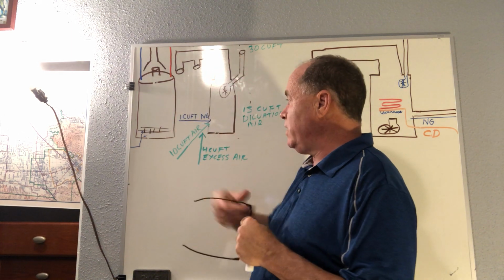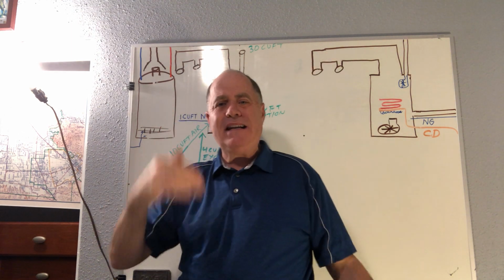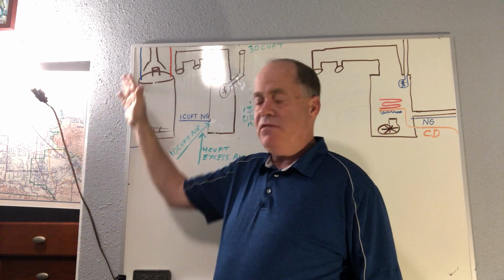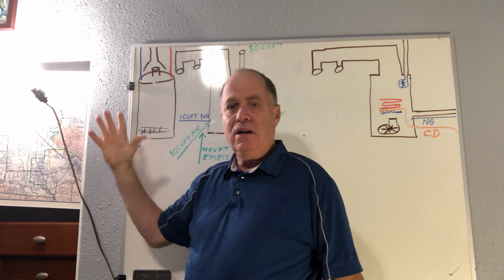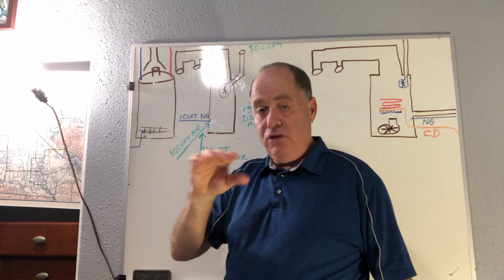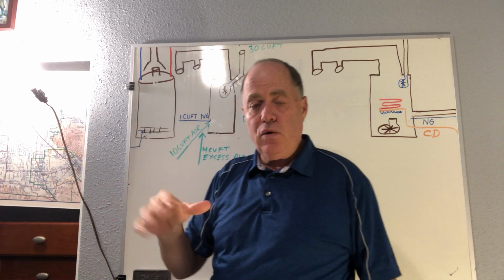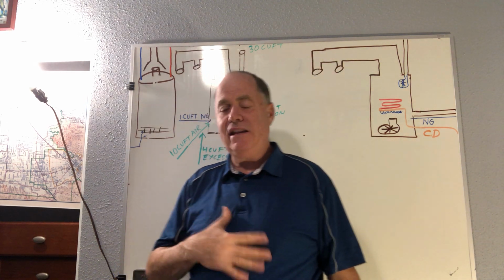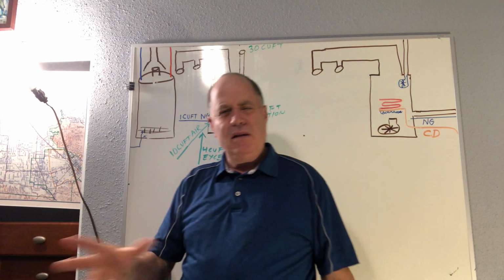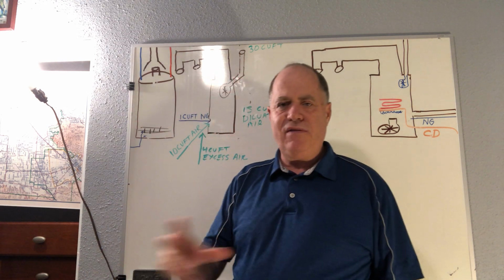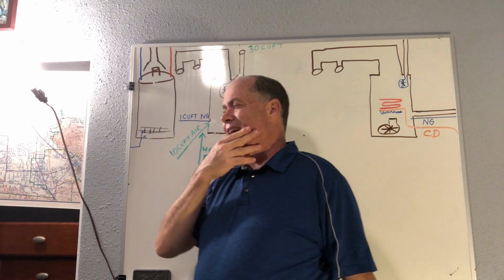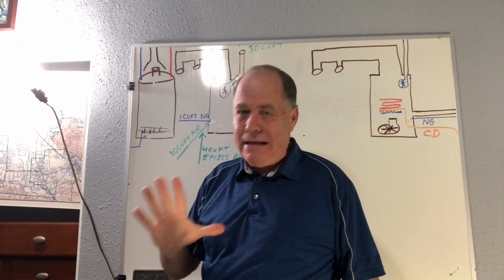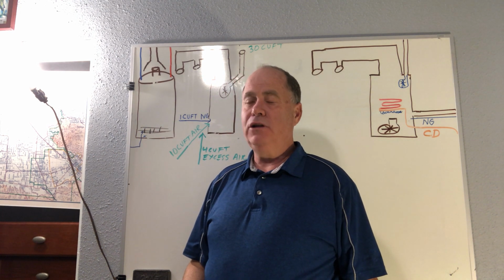And even just a point on hot water heaters, they've tried to make them more and more efficient, and they're called low NOx, low emissions. They're more efficient. They use less fuel. They heat the water very quickly. My personal experience with that, and they started coming out with these little different designs maybe 7-8 years ago, is that they're good, but they're a little more fragile.